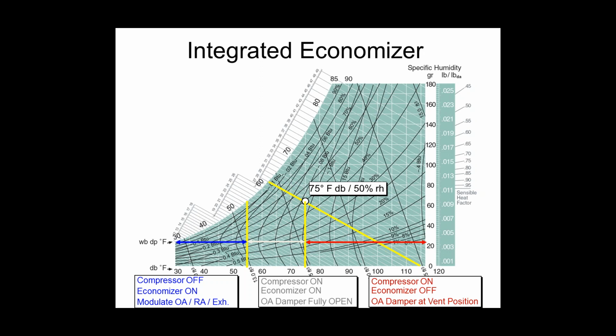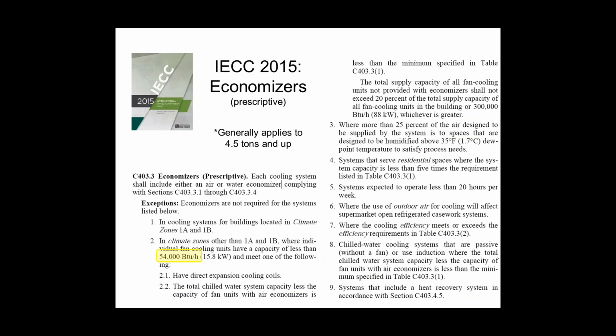Mark types in a question: why wouldn't you want to use an economizer on a rooftop that is less than 4.5 tons? You probably would, Mark. In our climate zone, you would, but you're not required to. And I don't know the exact history of why this just increased from 33 to 54, but personally I believe it's because of the small split systems, not because of the rooftops.